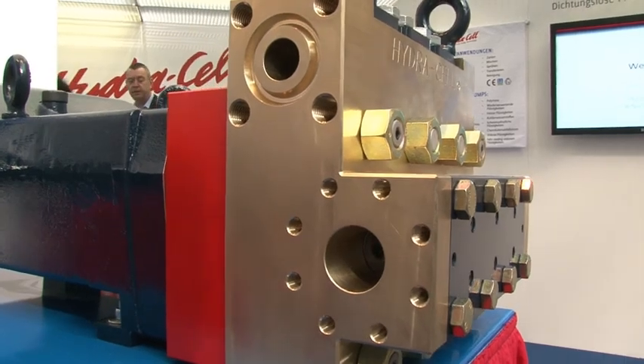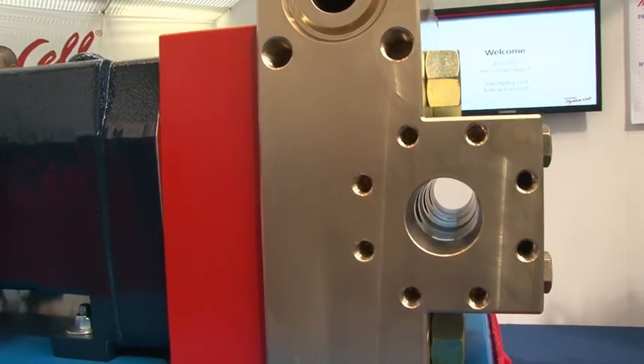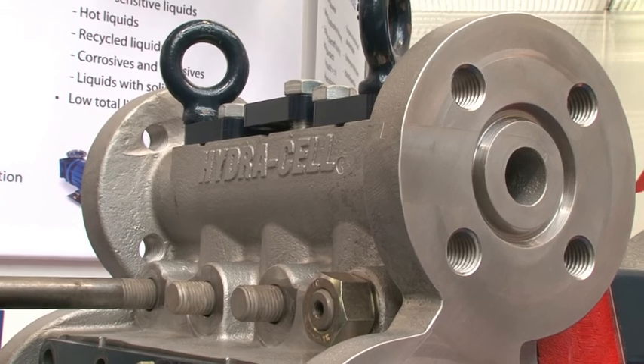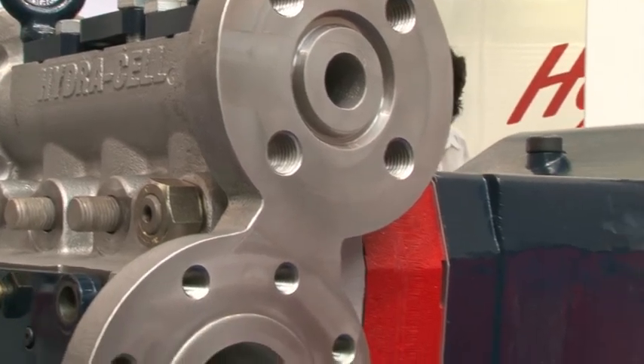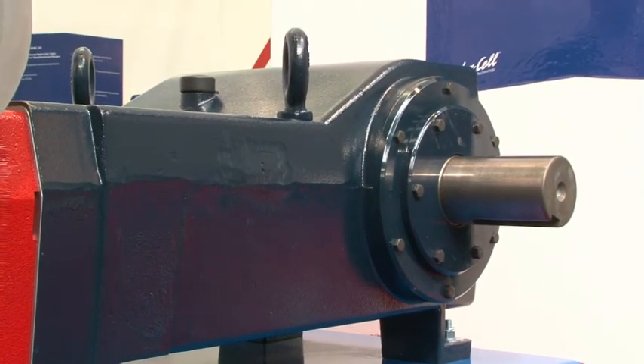With the new T-Series, you've raised the pressure envelope. Where will these new pumps be used? There are really good applications in the oil and gas industry, typically where they're pumping produced water — water with sand and also with aggressive hydrogen sulfide. Also non-lubricating materials such as methanol, used for methanol injection and de-icing. Triethylene glycol, which can be non-lubricating and as it's recycled, it picks up particles and is also H₂S aggressive, which attacks dynamic seals.